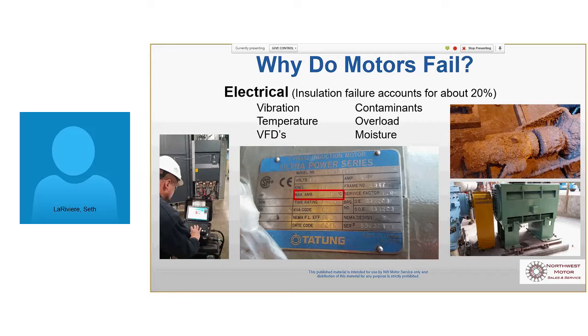So we put one of these in, and we're going to talk about temperature rise in a second. And I've got to admit, I'm a motor geek. I love motors, and the reason you're going to find out in just a second. This motor, it's all about temperature rise. So all motors are rated with an ambient rating. It's usually assumed to be 40 degrees C or 104 Fahrenheit, right? And most of the time, motors don't live in an atmosphere hotter than that, but not always.